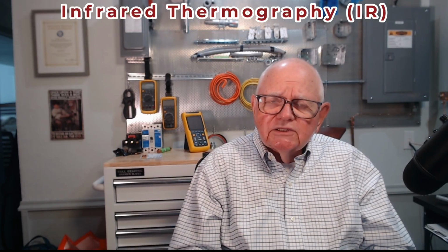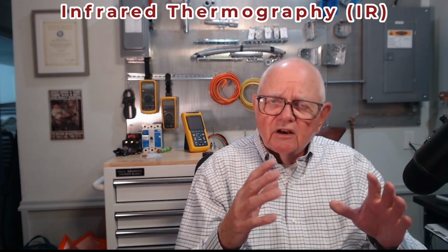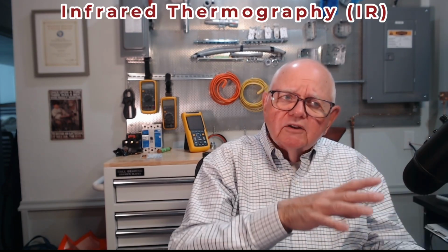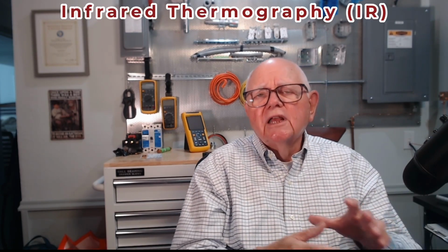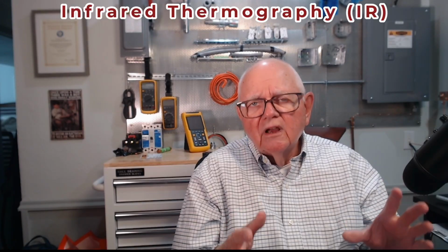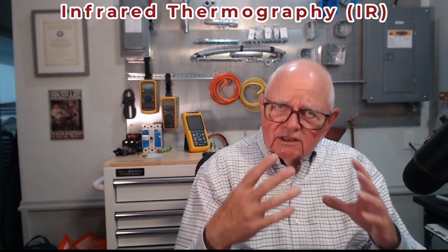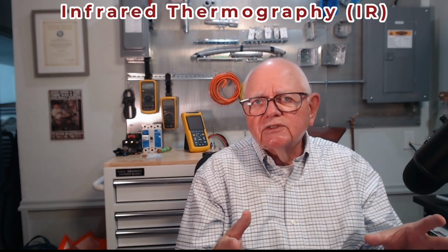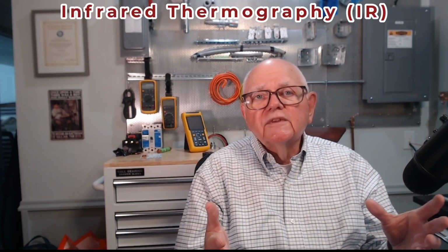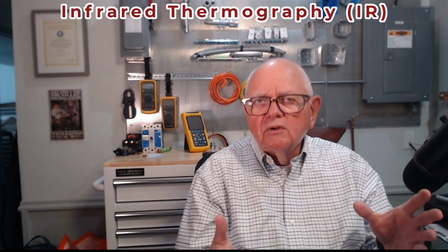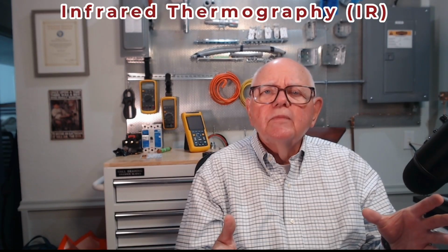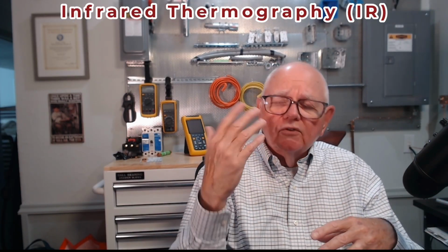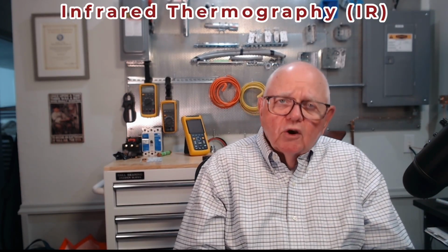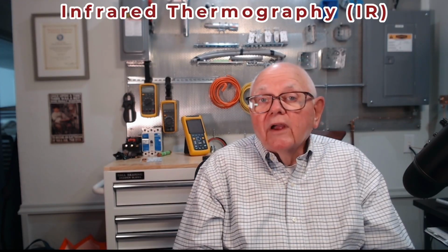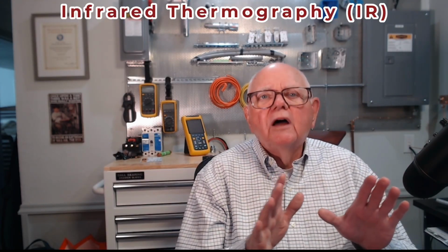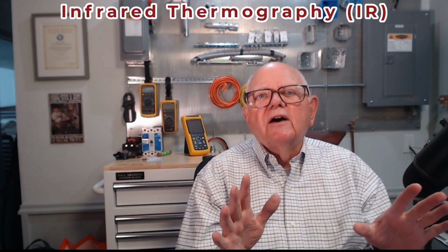The fundamental tests are what we've been talking about. We've talked about infrared thermography, we've talked about insulation resistance testing, and we talked about bolted connections. On the bolted connections, we can look at temperature, infrared, or temperature sensors. We can torque with a calibrated torque tool to 90% of that original value. We can measure the resistance through the bolted connection with our low resistance ohm meter. Now, that's fine on our low voltage, less than 1,000 volts equipment.